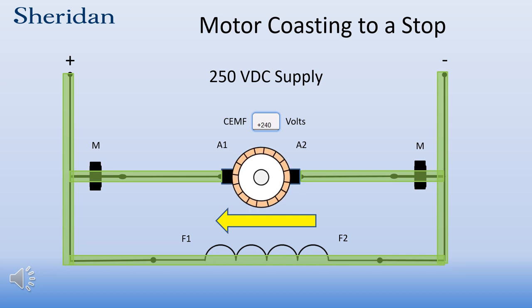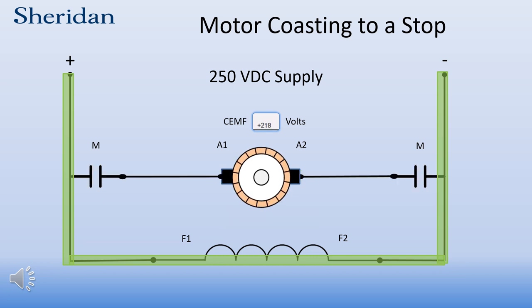When the M contacts open, current no longer flows through the armature and the armature coasts to a stop. The energy of the armature is lost through friction of the bearings, the mechanical load applied to the motor, and the movement of air caused by the armature. Because the shunt field is still energized, counter-EMF is still generated in the armature and diminishes as the armature slows.